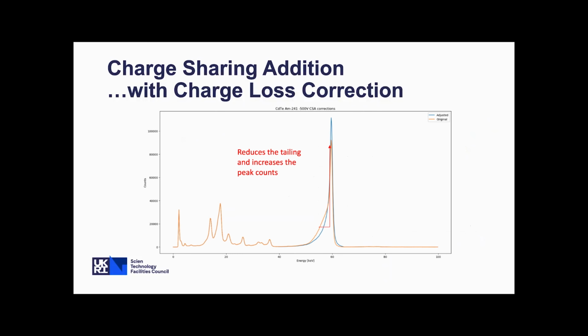So here we've got the charge sharing addition corrected spectrum in orange. When we add that correction factor in, this tail is reduced and those values are corrected backwards into the peak. So this gives us a boost in peak height and recovers the spectral resolution of the detector as well.